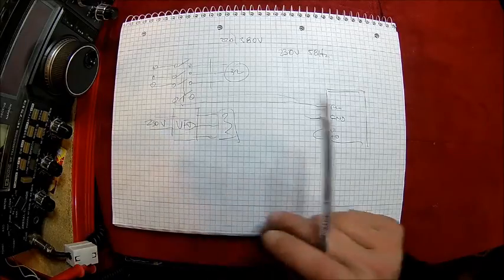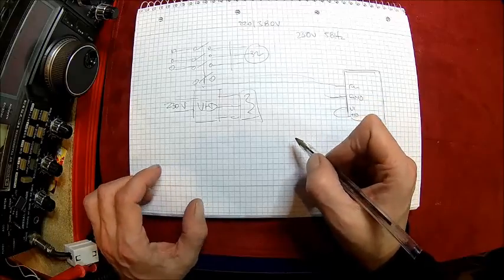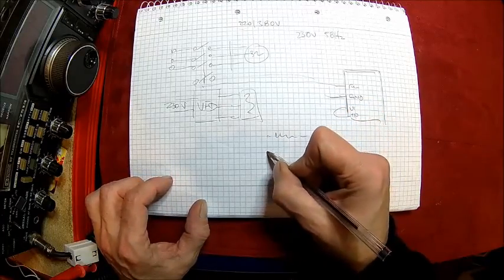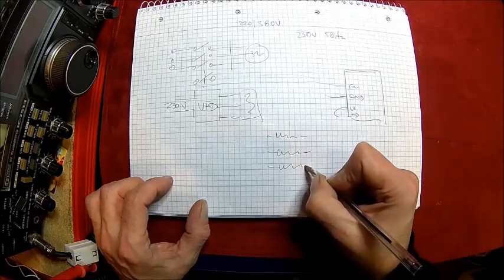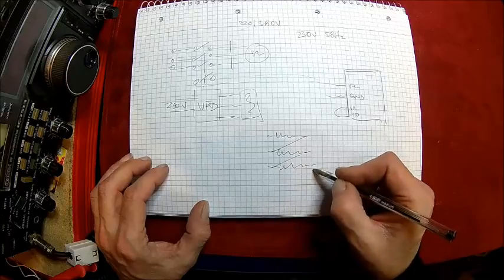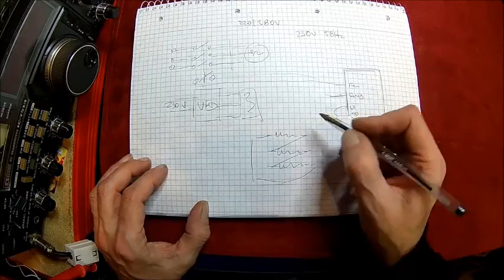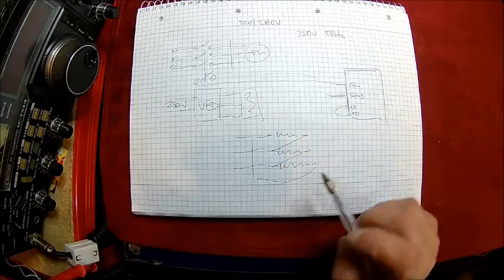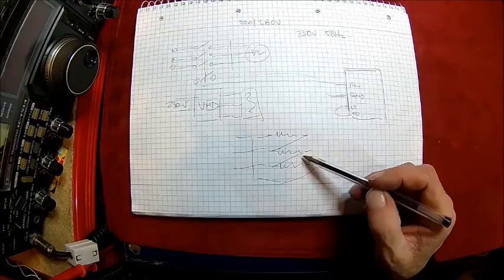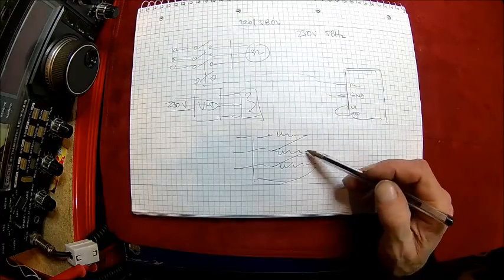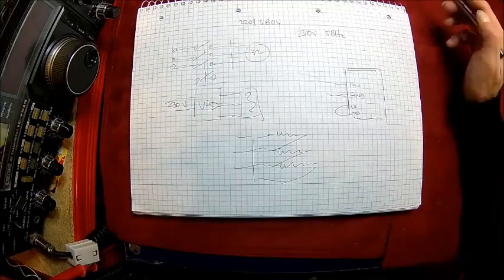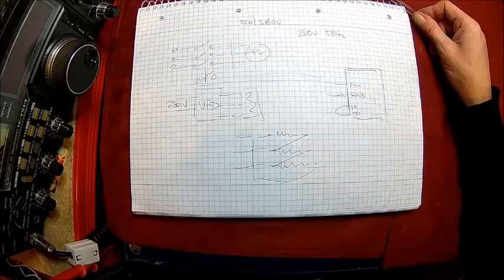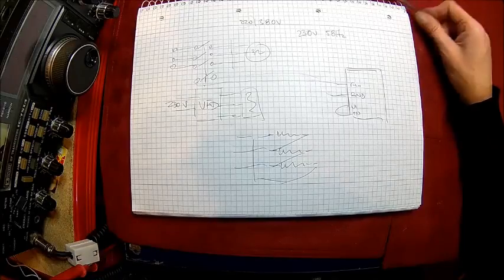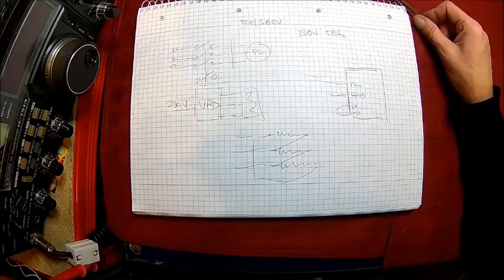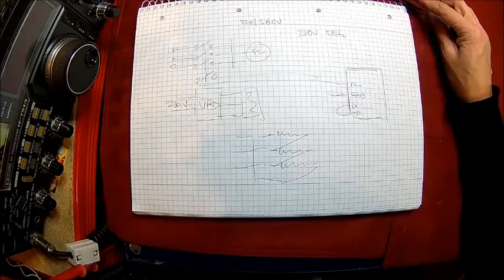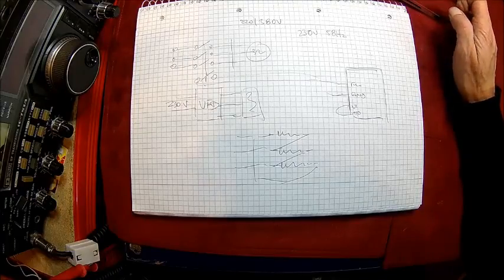from a 230 volt input, because if you look at the transformer, it is wired in delta, so we have 3 coils of the transformer, and they are all wired in delta. So the phases go here, here and here. So for the drive, for the inverter, it doesn't really matter if this is a drive or a motor, except the drive can do vector mode, so this needs to be turned off. The drive has to be run in voltage frequency mode, which all these cheap drives usually do anyway. I just found out there is no option for vector or field oriented control or something like that. It just doesn't do it, which is good for what we're going to do.